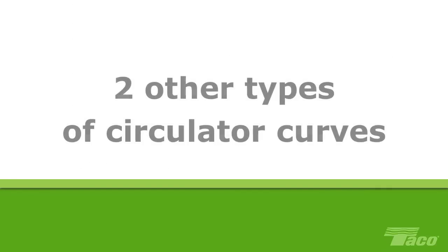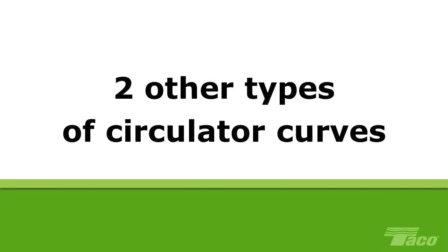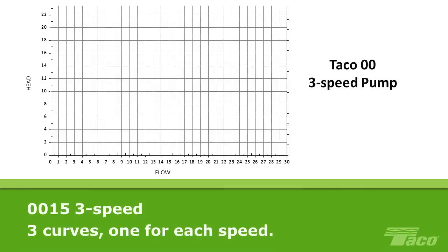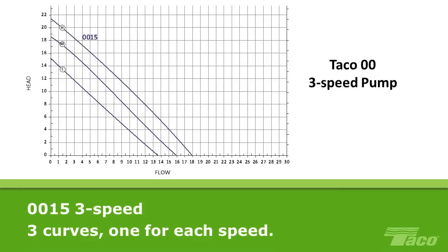That covers fixed-speed circulators, but we also need to look at the curves of two other types of circulators used in residential jobs. The first is the 3-speed pump. This curve is for the Taco 0015 3-speed cartridge circulator. The curve for a 3-speed pump actually consists of three separate curves, one for each of the pump's speed settings. The pump can operate on any one of these curves, but not between them.